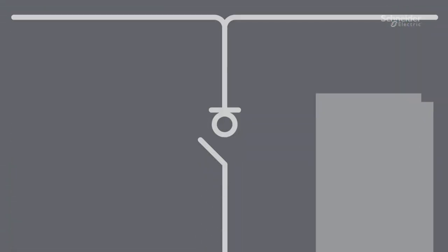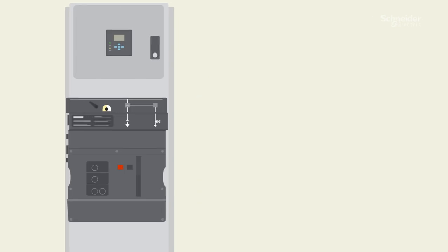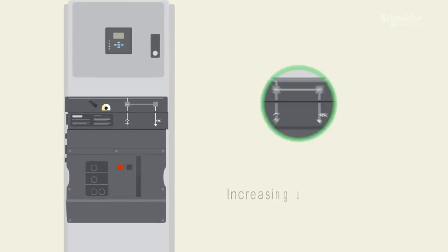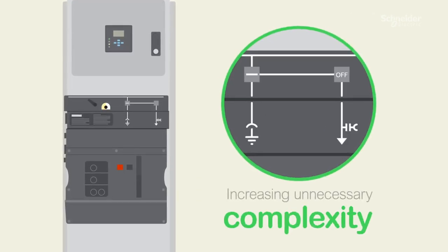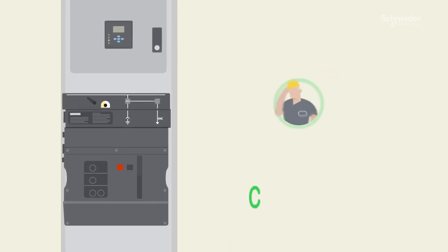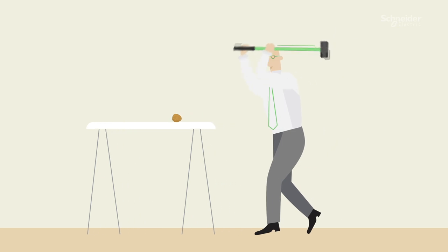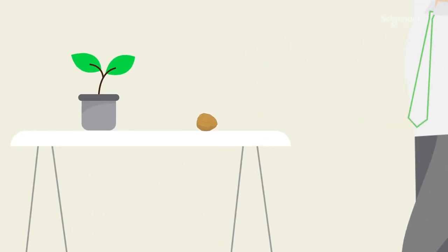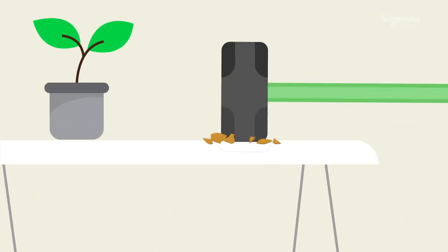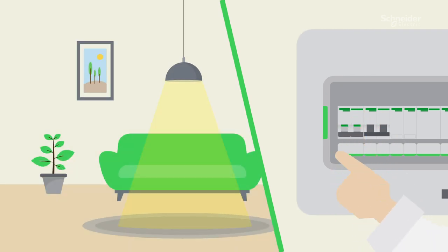Removing SF6 from switchgear is possible. In secondary applications, that often means replacing the SF6 switch with a vacuum circuit breaker. But this has three main drawbacks: it makes the equipment more complex and bigger, fuse protection of a transformer is not possible, and operators are forced to change the way they work. All this means that circuit breakers are not cost-effective and commonly overkill for simple needs. Think of your house - you wouldn't use a circuit breaker to turn on a light.